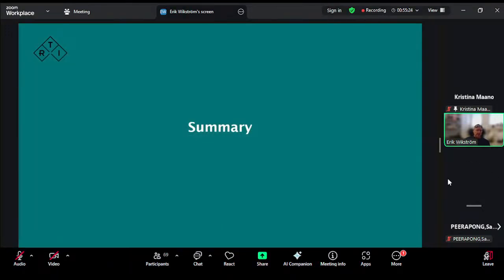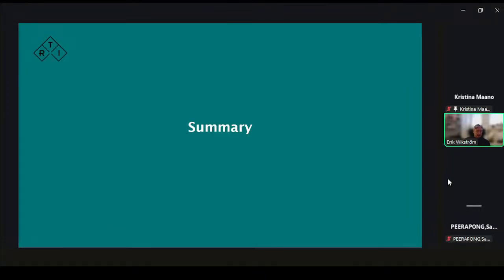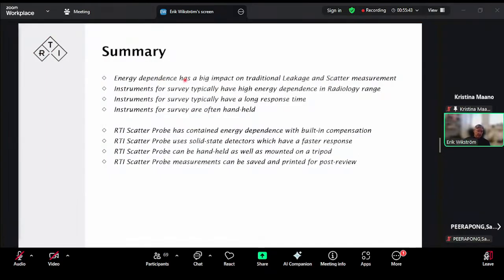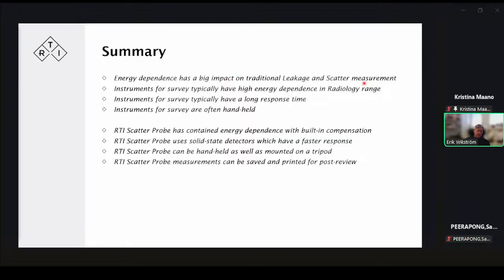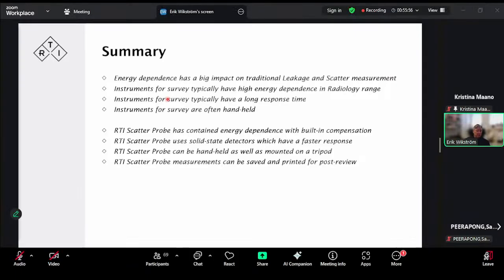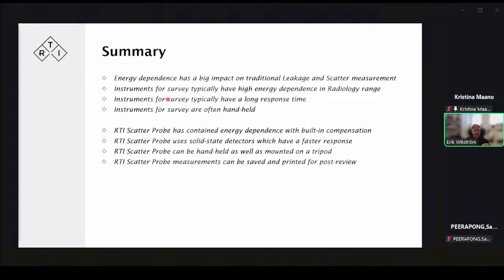So just to summarize what we've spoken about here, scatter and leakage measurement is quite important. It's necessary to be done. It's required by many regulatory bodies. But we need to keep in mind that energy dependence has a big impact on traditional leakage and scatter measurement instruments. They have a long response time, typically 2 seconds or more, even if the radiation is weak and the dose rates are low. And many times they're designed to be operated by hand. Those are the challenges that we see.